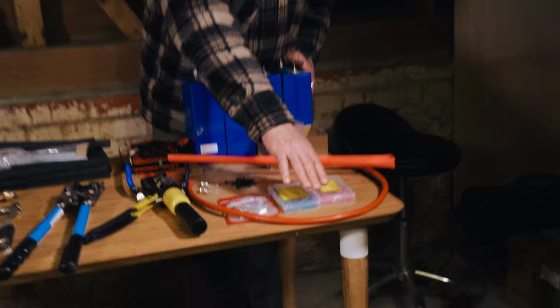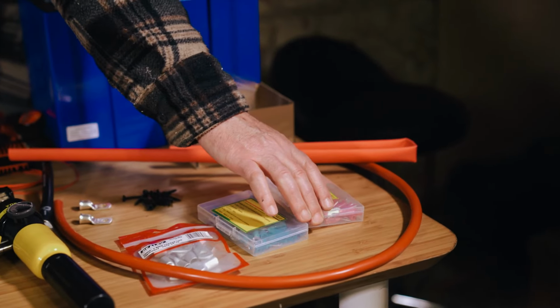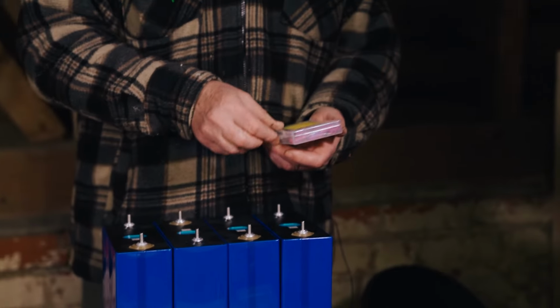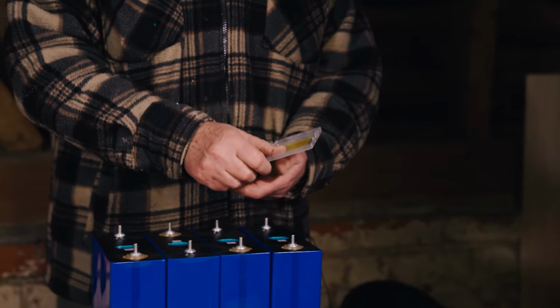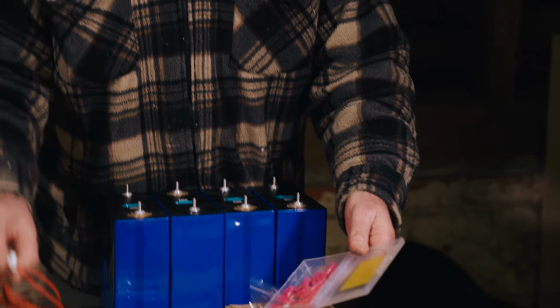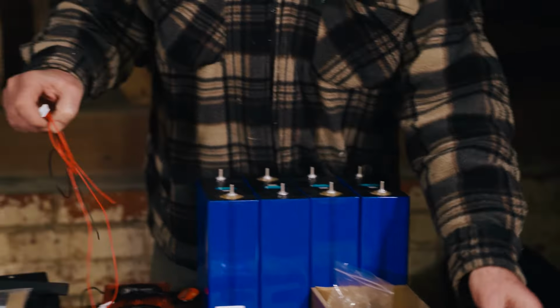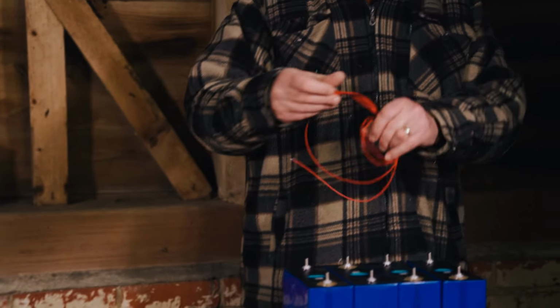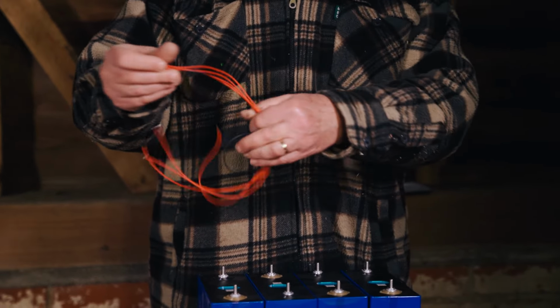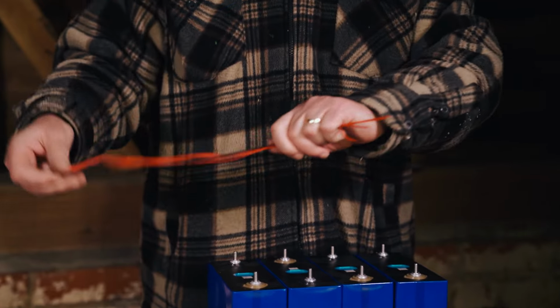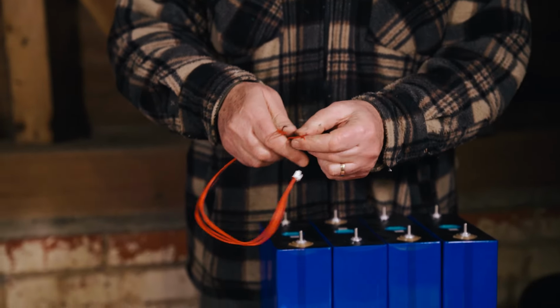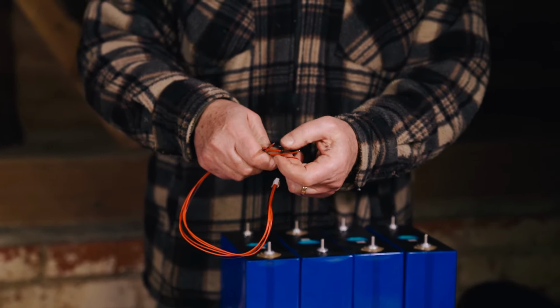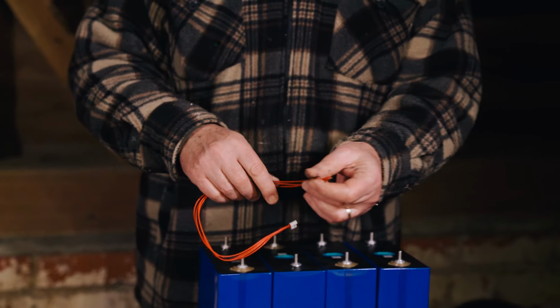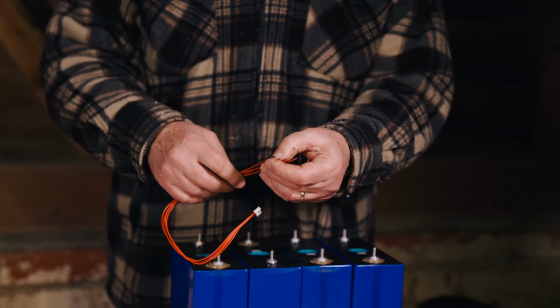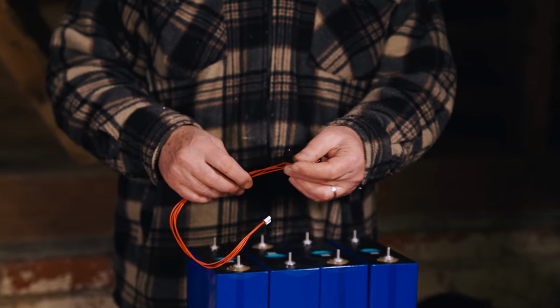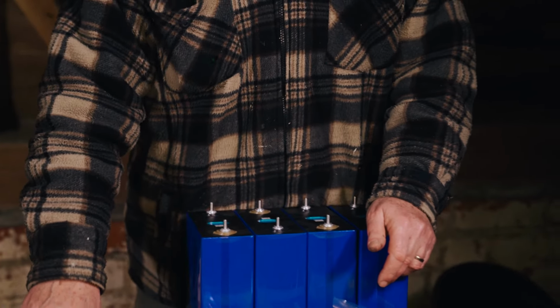Continuing with all of these things, you're going to want some terminals to terminate the balance leads. If you have a look at the balance leads, they're just bare wires at the end. You're going to need to cut back a little bit more of the insulation and terminate all 5 of these - 1 black and 4 red. We're going to take you through that process in detail.